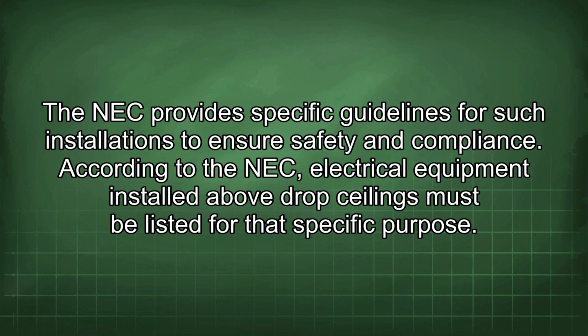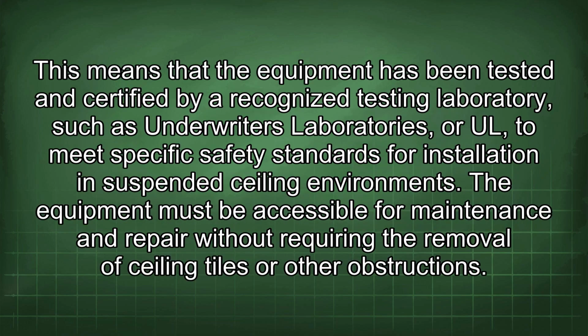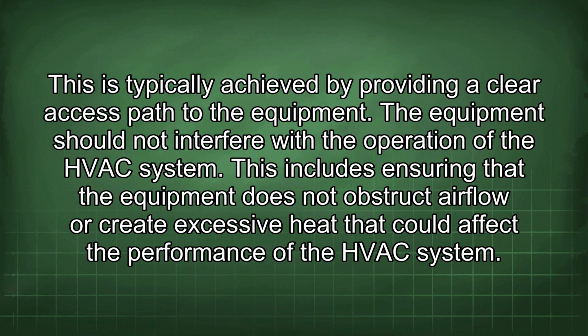According to the NEC, electrical equipment installed above drop ceilings must be listed for that specific purpose. This means that the equipment has been tested and certified by a recognized testing laboratory, such as Underwriters Laboratories, or UL, to meet specific safety standards for installation in suspended ceiling environments. The equipment must be accessible for maintenance and repair without requiring the removal of ceiling tiles or other obstructions. This is typically achieved by providing a clear access path to the equipment. The equipment should not interfere with the operation of the HVAC system. This includes ensuring that the equipment does not obstruct airflow or create excessive heat that could affect the performance of the HVAC system.